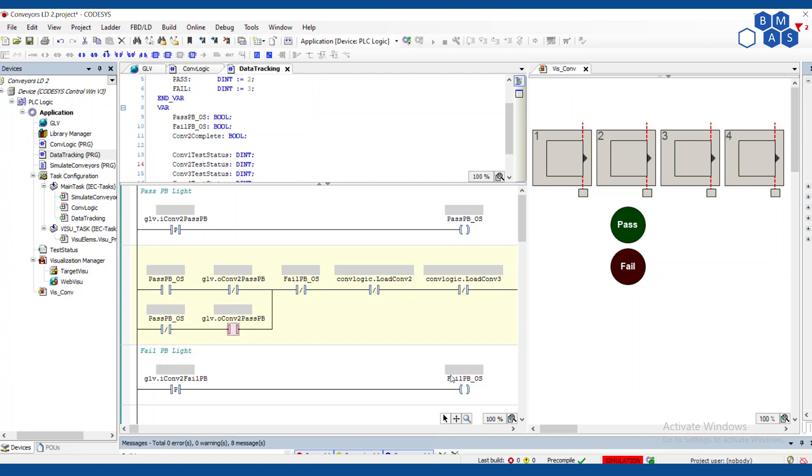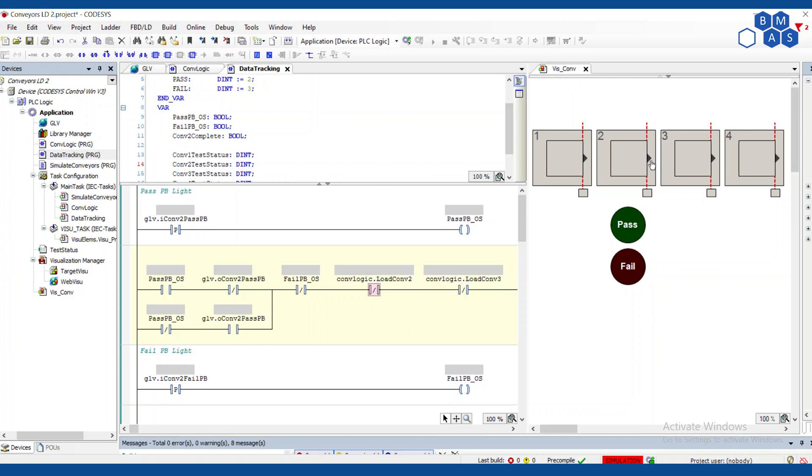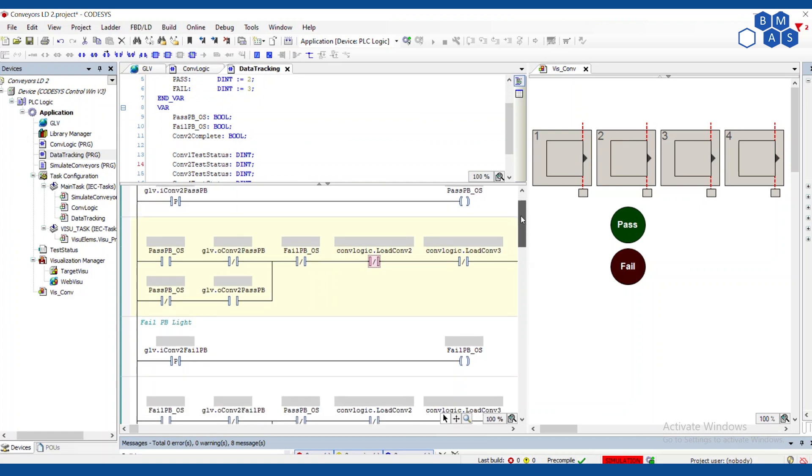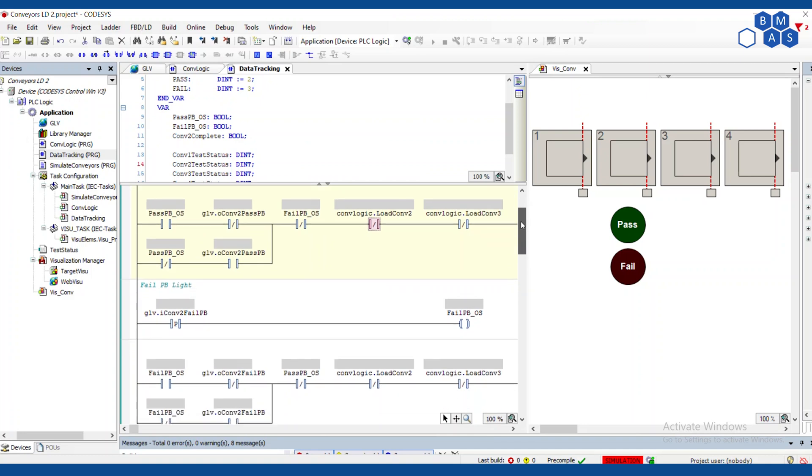We also want this to clear when we're done moving a part out of station two should clear itself, or rather when we start moving the part out of station two, because at that point this should just reset. So as soon as we're loading conveyor two or conveyor three, as soon as something is moving on these conveyors that affects conveyor two, clear that. And we've done the same thing for the fail button as well. They're identical, except obviously pass and fail.